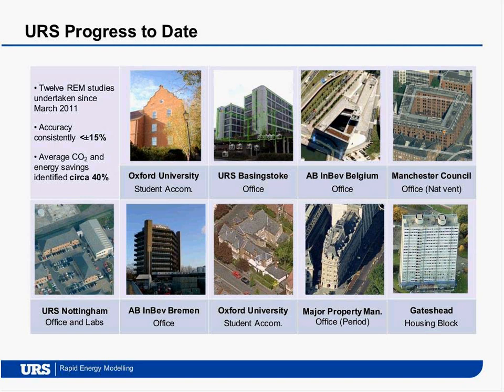To date, we've actually done around 15 different buildings around Europe, mostly in the UK, but of all different types. When we form the model, we then calibrate the results each time against the actual usage from billing data. We find consistent accuracy within plus or minus 15%.